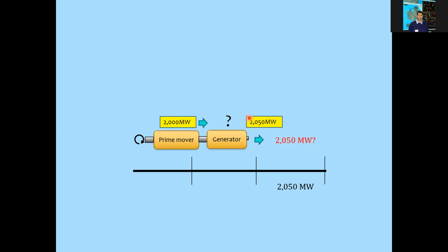In fact, generators can do this - how it's happening I will not tell you now, it's not the time, I don't have the time. But take it from me, and if you're not sure, I can give you textbook references: generators can increase their electrical power output almost instantaneously to follow consumer demand at its terminals. So in effect, my generator is now giving 2050 megawatts, but it is not getting 2050 megawatts from the prime mover. So how is this possible?